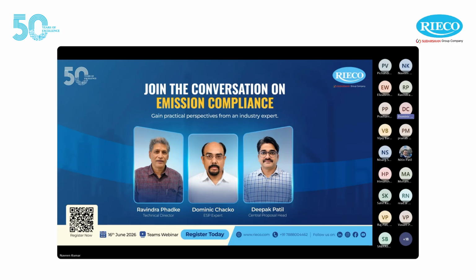And as you know, ESP electricals is all about how resistive the dust is. And if that happens, then the performance of the ESP is going to go down. So that's one thing, beyond the limits of the flanges of the ESP, that happens and affects the performance of the ESP: false air leakages. So one should be very alert to this aspect of the process.